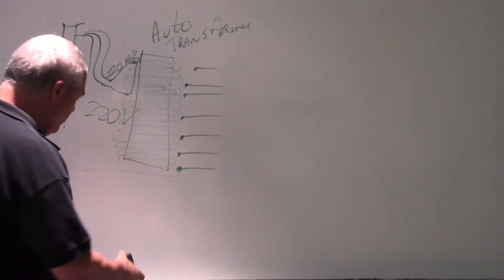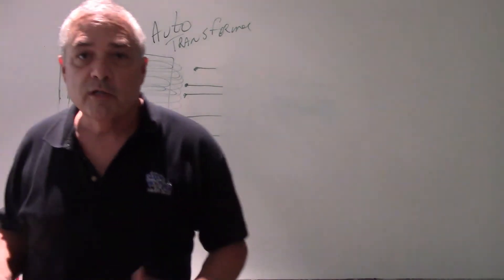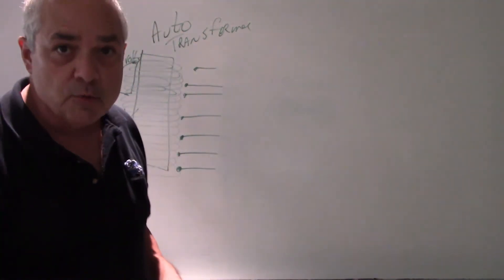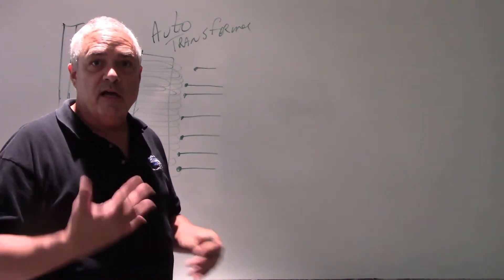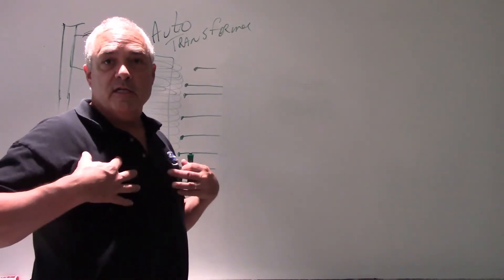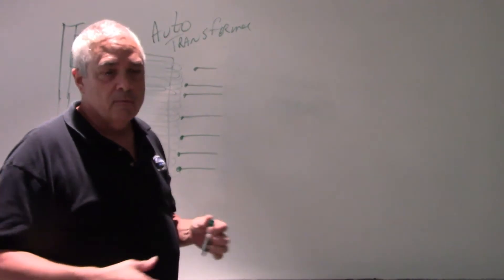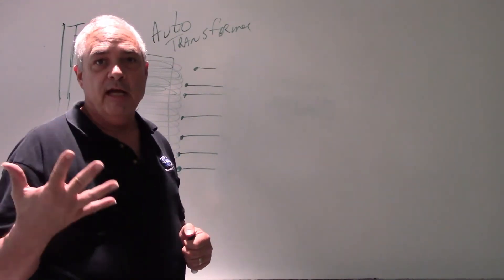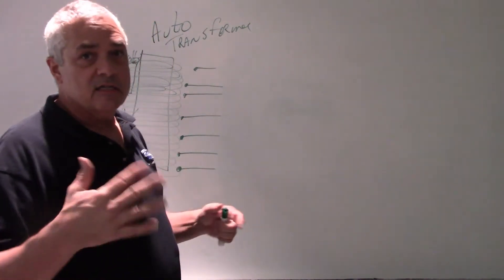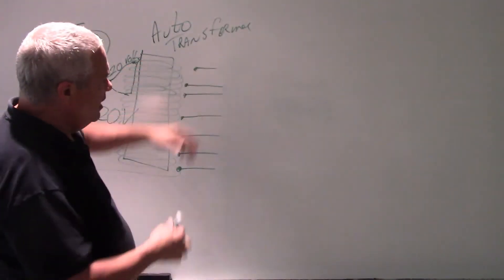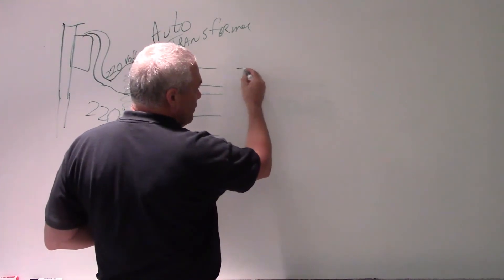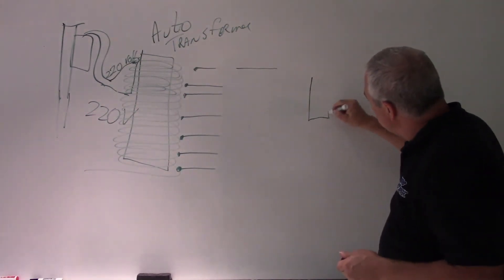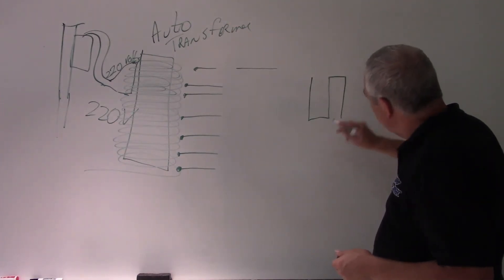Now we've got voltage coming off the auto transformer, but we need a lot of voltage — 80,000 volts, 100,000 volts, 120,000 volts — depending on what kind of X-rays we're doing. For an abdominal series we might need 90 kVp; for a chest X-ray probably 120,000 volts; for a hand, just 60 kVp. So we select the right voltage, and coming off the auto transformer, we feed into a device called a high voltage transformer.